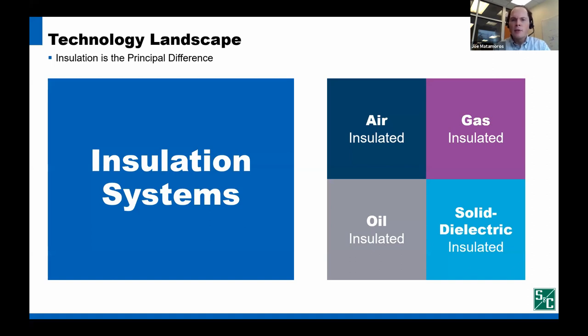Insulation systems are the principal technology differences between switchgear technologies. These insulation technologies impact how the interrupting devices and schemes function, the available electrical ratings, and the features and functions of the switchgear. There are four principal underground distribution switchgear insulation technologies. The first technology is air insulated or unsealed gear. There are three categories of sealed gear: oil insulated, gas insulated, and solid dielectric insulated.